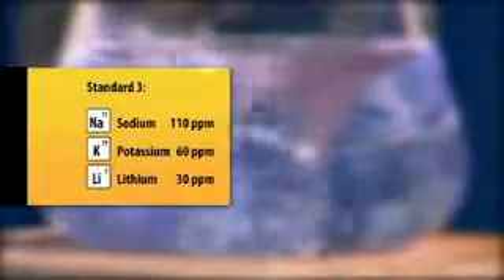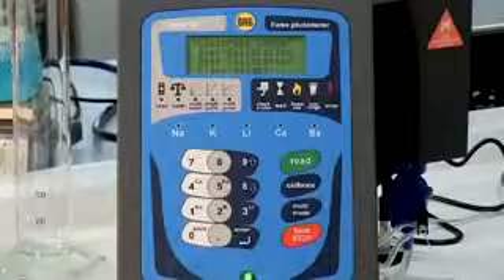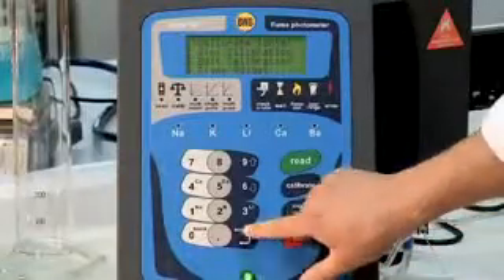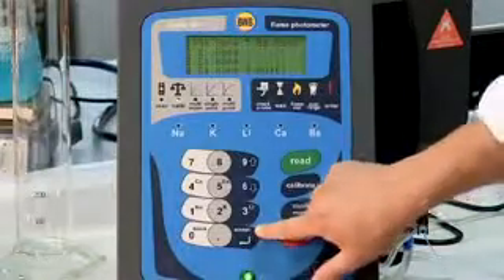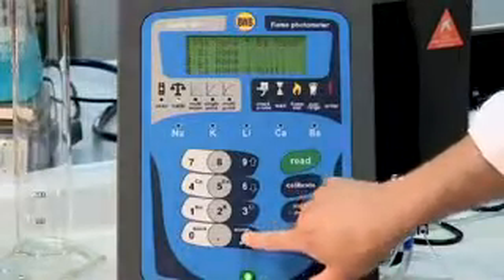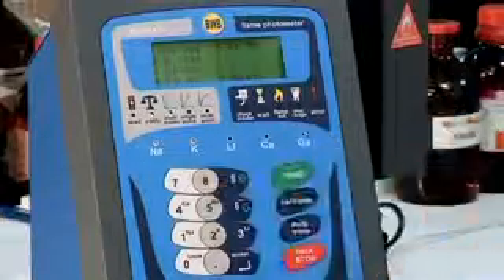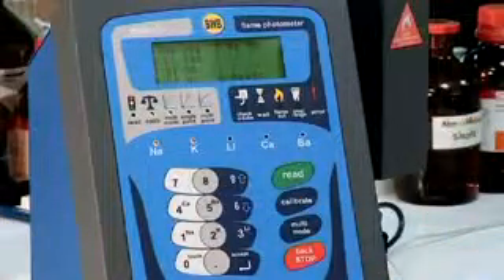The Bwb Xp allows us to enter as many as 14 calibration points plus the blank, so we can bracket our expected unknown sample values very closely, thereby increasing the precision and accuracy of the readings. The process is similar to the single point calibration, but when we are prompted for the number of points, we will enter 3. Run the blank as before. For our first standard, key in 40. Start aspirating the 40 ppm potassium standard.